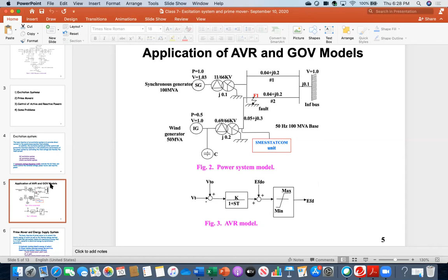This means that ultimately, by controlling the DC field voltage, it is maintaining the voltage here. The AVR is continuously monitoring this position. Is there any difference or not? If no difference, then fine. If there is a difference, then it takes action, I mean, it adjusts the field voltage.